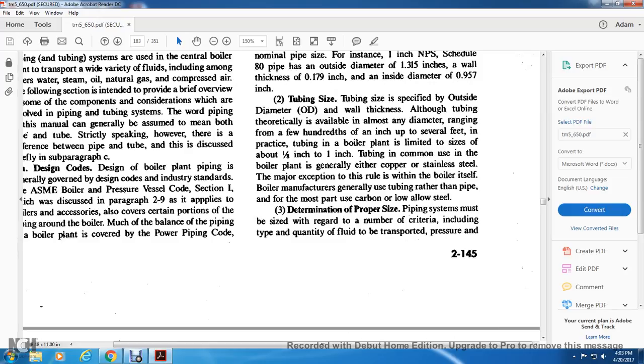And tubing in the boiler plant is limited to sizes of about 1/8 of an inch to 1 inch. Tubing in common use in the boiler plant is generally either copper or stainless steel. A major exception to the rule is within the boiler itself. The boiler manufacturers generally use tube rather than pipe.